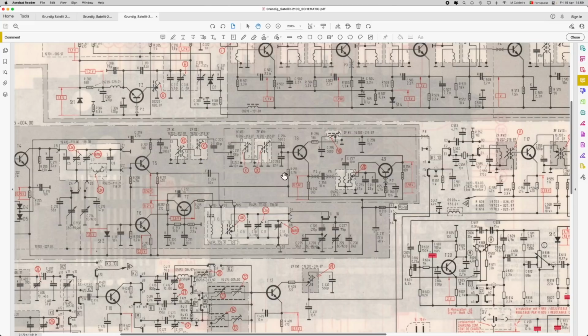So what are we doing here? We're sending 2 megahertz in here, and we want to make sure that it comes out of here peaked at 460. So we have to adjust the oscillator. And what we're really doing is making sure that this oscillator is adjusted to 2.460 megahertz. So 2.46 megahertz adds or mixes with the 2 meg you're sending in here, and you get 460 coming out here, and that goes through the whole 460 IF block. That makes sense. So we'll do that.